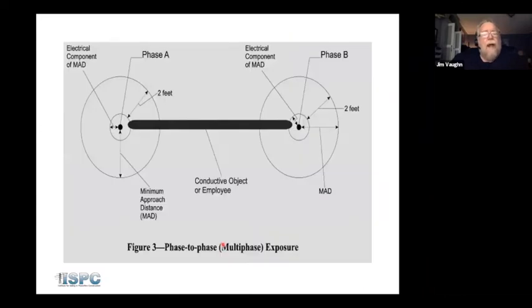Now, we also have to clearly understand how we calculate MAD based on either line-to-ground voltage or phase-to-phase voltage. A lot of people misunderstand this, so I'm just going to give you a definition and a graphic that comes from OSHA. What OSHA says is we have the MAID, represented by the small circle in the middle. This is the conductor, and we have the MAD, which represents the inadvertent movement.